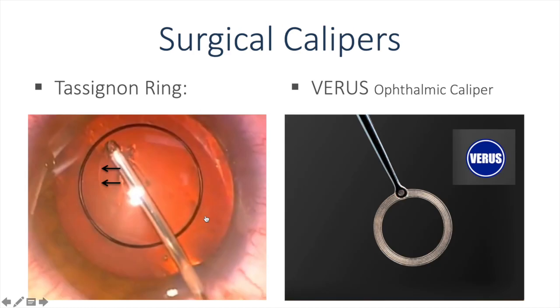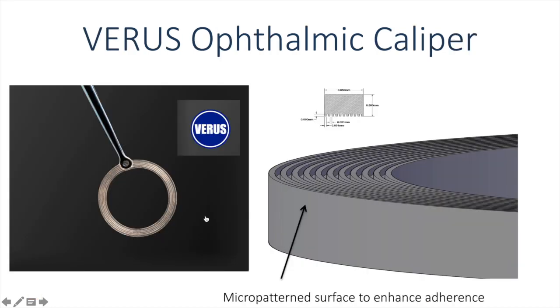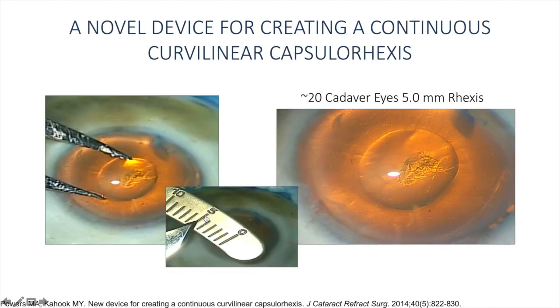The last category is surgical calipers. A device more prevalent on the European market is the Tassignon ring, which is placed on the capsule and used to visually guide the capsulorexis opening. The VERUS ophthalmic caliper is a device that came out of my laboratory at the University of Colorado. It allows for walking the capsulorexis along the inner edge to produce a well-centered and perfectly round capsulorexis. We created this device with a micropatterned surface on both sides to enhance adherence to the capsule. We published results of the preclinical work in the Journal of Cataract and Refractive Surgery in 2014, demonstrating a reproducible 5 mm capsulorexis in cadaver eyes. This gave us faith to move the project forward, and we eventually commercialized this product in the United States and internationally.